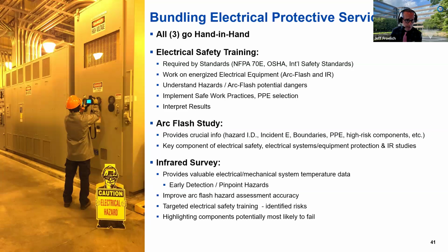Vice versa, the infrared study can provide good guidance for the arc flash study as well. The infrared study will target those abnormal temperatures, help early detect and pinpoint hazards, improve the accuracy of the assessments, and give you targeted assets to make sure you have the right risks identified and safety training for. It's going to identify potentially those items and assets more likely to fail than others based on temperature and other conditions.